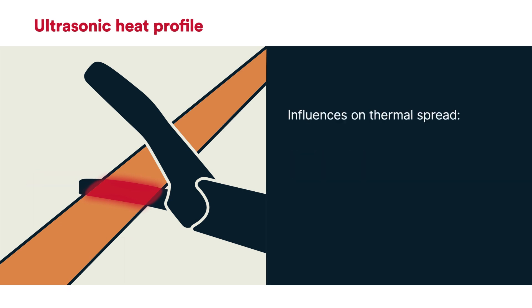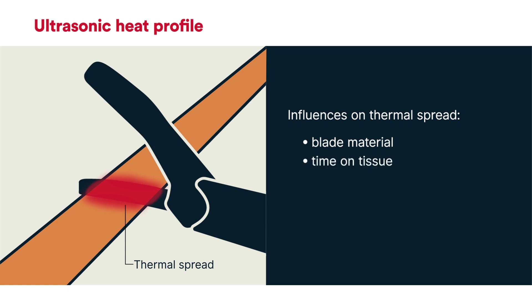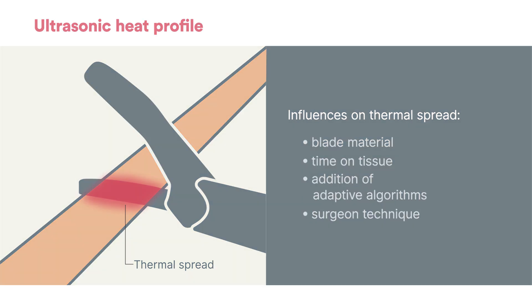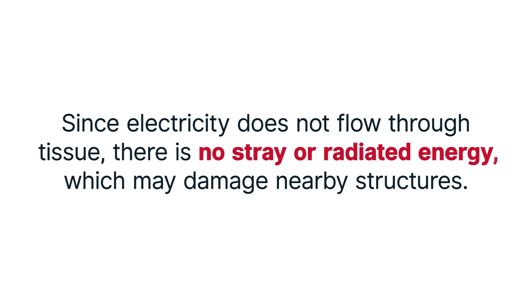Heat is generally contained within the jaws of the device, extending laterally by a few millimeters. The amount of lateral thermal spread is dependent on the blade material, time on tissue, addition of adaptive algorithms, and surgeon technique. Since electricity does not flow through tissue, there is no stray or radiated energy which may damage nearby structures. This is an electrical phenomenon of bipolar devices, which will be covered in Video 4 of this video series.